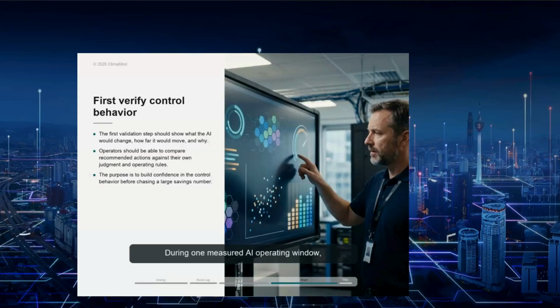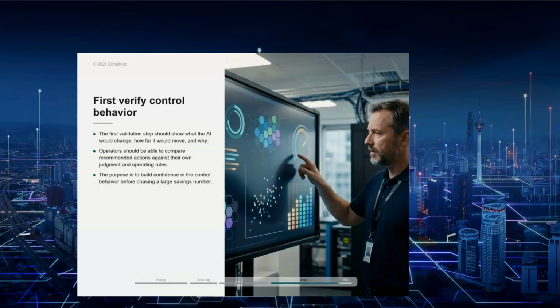During one measured AI operating window, average plant efficiency improved from 0.74 to 0.65 kilowatts per ton, or 12.11%. The method matters. Show how we would control, keep boundaries clear, protect operation, and compare energy use against normal operation. That is the proof pattern. Focused scope, clear control boundary, simple energy metric, and before and after comparison.